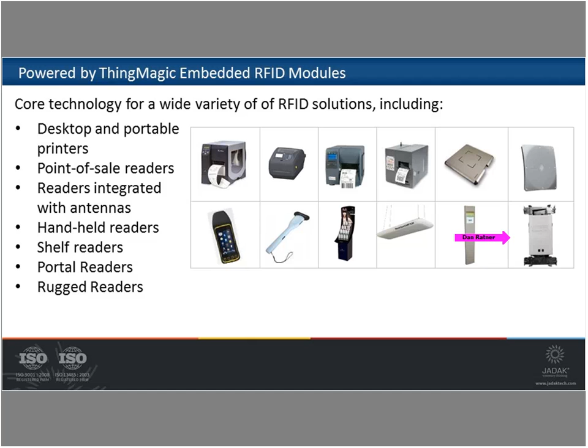First up is the JADAK handheld reader platform. In order to simply and efficiently add barcode and RFID scanning to medical devices, JADAK developed handheld readers that appear as a keyboard entry device to PCs, providing both barcode and RFID information to the host. The reader can be either tethered directly to the device via a USB connection, or the device itself can be Bluetooth enabled, transfer its information wirelessly to a base plate, and then that base plate is tethered to the medical device.